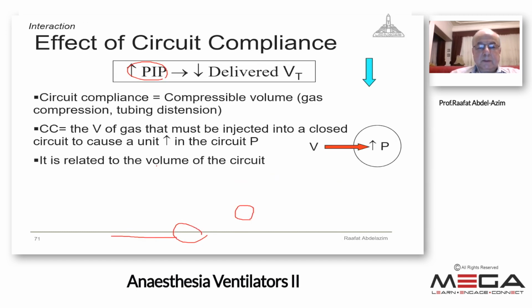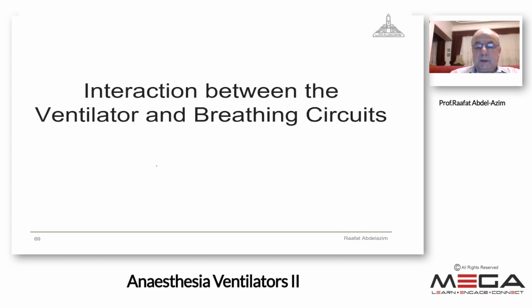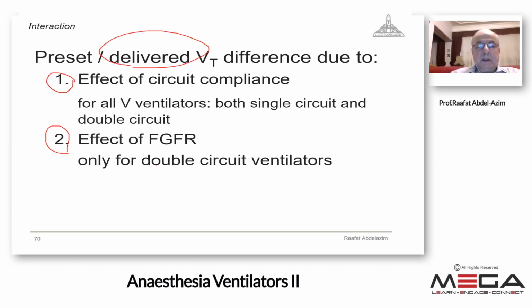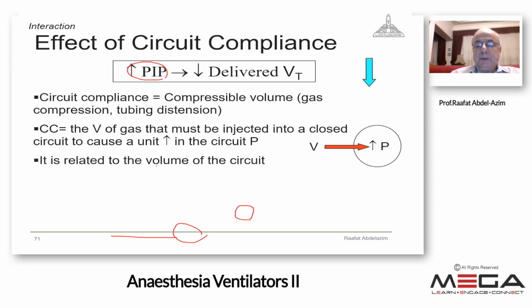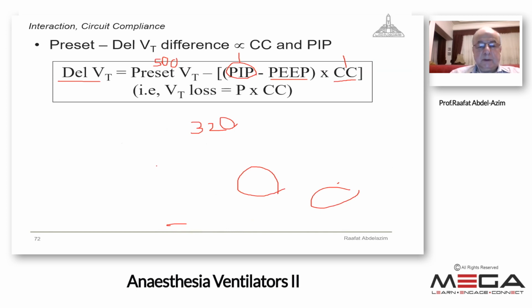Again, the interaction between the ventilator and the breathing circuit is the relationship between the preset and the delivered tidal volume. There is a difference. Some part of the tidal volume is lost due to the effect of circuit compliance, and some part will be added due to the effect of fresh gas flow. The effect of circuit compliance depends on the compliance of the circuit, the material itself, and the peak airway pressure. The higher the compliance, the more loss, and the higher the peak airway pressure, the more will be lost from the preset tidal volume.